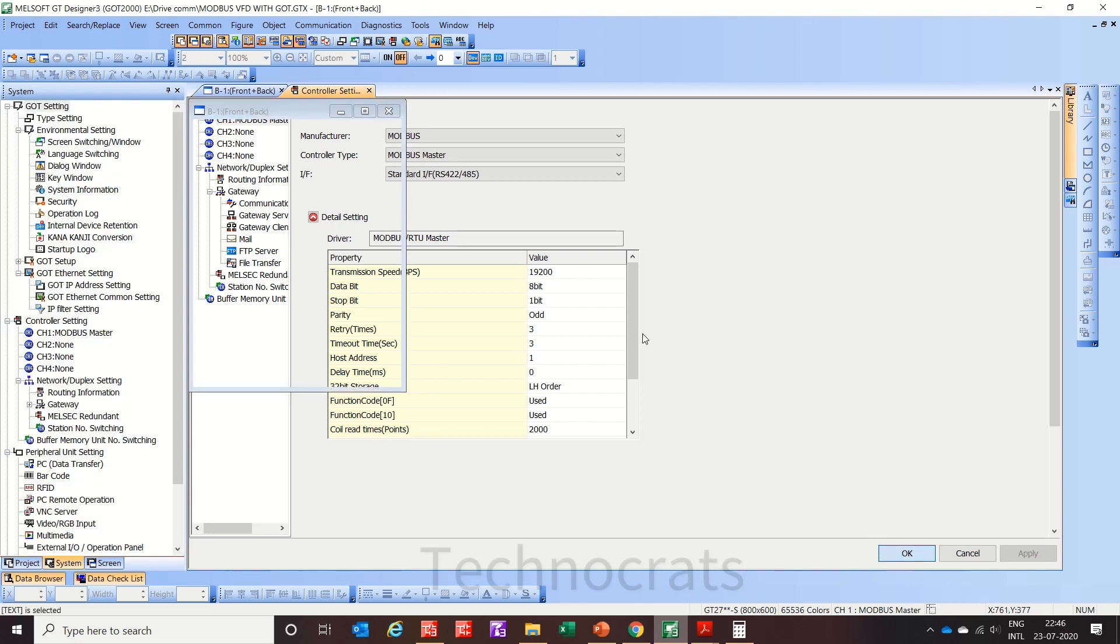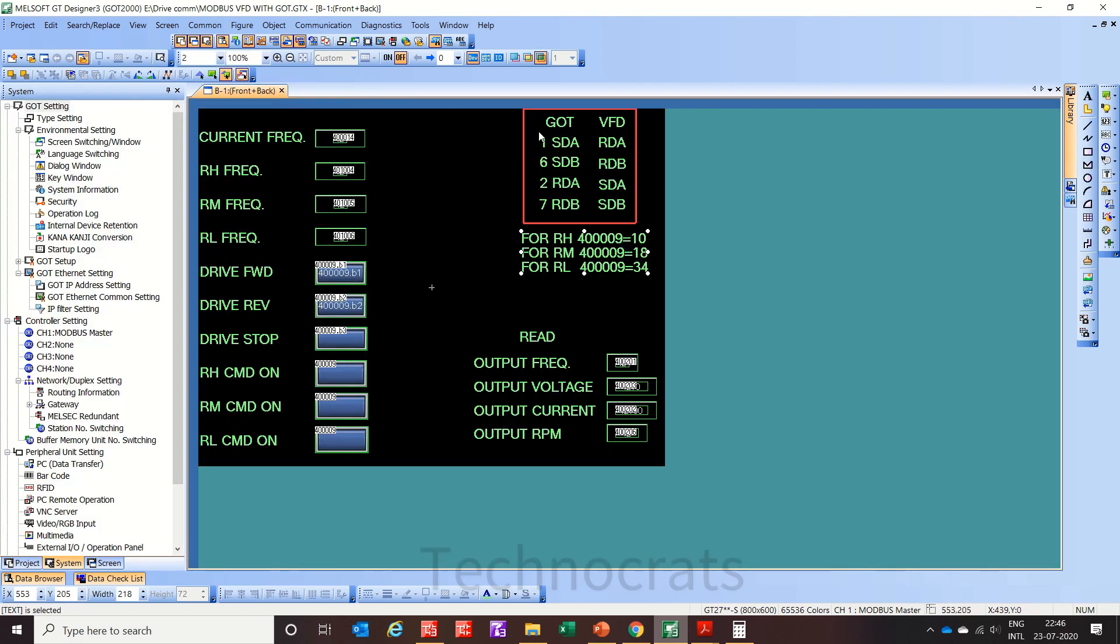Now I will show you the wiring system. Here in wiring for GOT 1, 6, 2 and 7 are the numbers, and regarding the VFD, SDA connected to RDA, SDB connected to RDB, RDA is connected to SDA, RDB is connected to SDB.